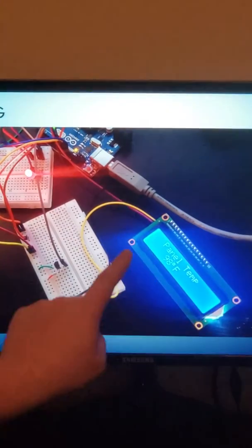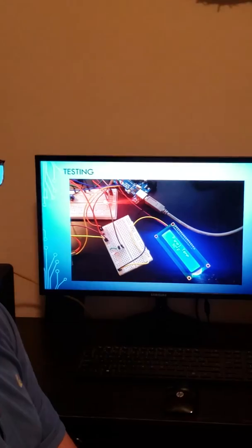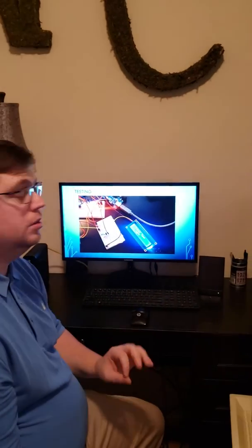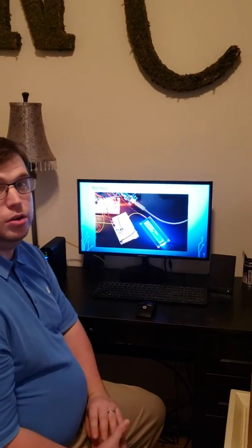This is the alarm state. We're over 95 degrees Fahrenheit, so we have a red LED. The speaker should be warbling in an alarm state to alert the operators and maintenance that this is in an over temperature state.